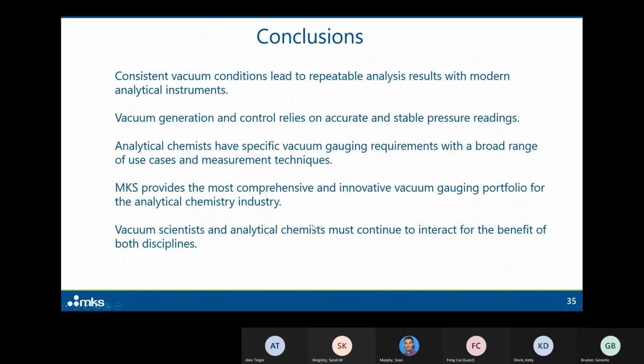As a conclusion, I hope this gave you an idea of the number of variables and the amount of work that goes into developing a product line for any industry, in this case particularly the analytical market. I wanted to bring back the idea that consistent vacuum conditions are required to get repeatable analysis results in modern analytical instruments. To have good vacuum generation and good vacuum control, you have to have accurate and stable pressure readings in your systems. So pressure measurement is critical.